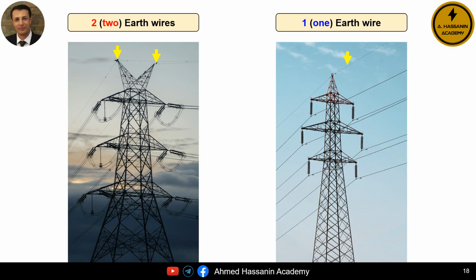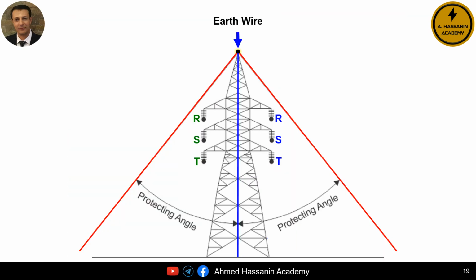Next, we come to the last point, which is that sometimes we find that some overhead transmission lines have only one earth wire installed, while other overhead transmission lines have two earth wires. So why are there two earth wires in some cases and only one in others, and what is the difference between them? As I mentioned earlier, the primary function of the shield wire or earth wire or ground wire is to protect the phase conductors and the insulators of the overhead line or the tower insulators of the transmission line from lightning strikes. But we must understand that the earth wire protects a specific area, or in other words, the earth wire has a certain protection angle.